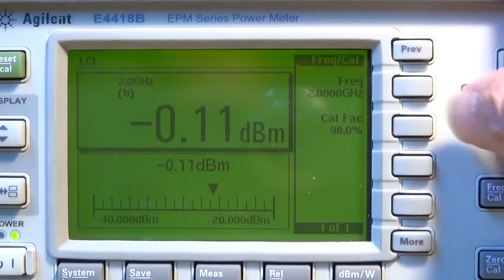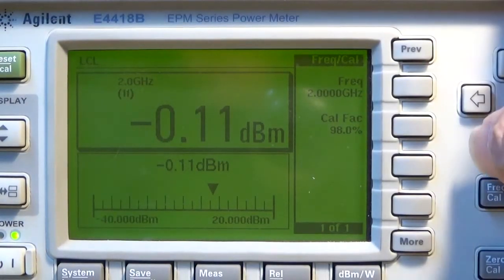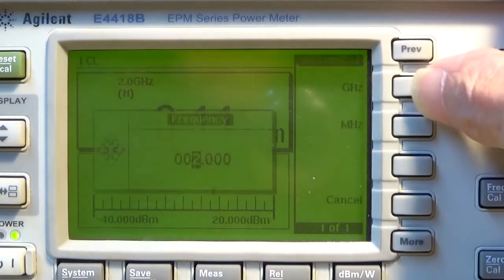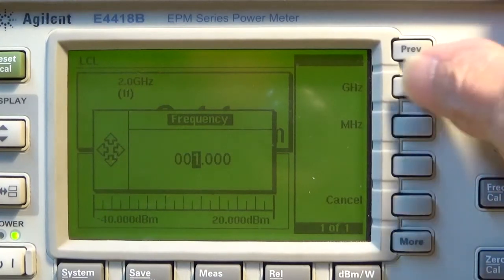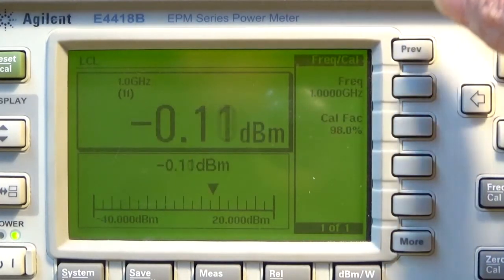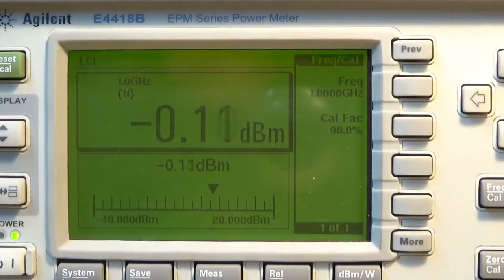Okay, now I've got to go through all this procedure again. Set it to 1 gigahertz, and it's minus 0.1 dBm. I think that's a reasonable output for an RF generator, because even they're not guaranteed more than about plus or minus 0.5 dBm accuracy across that whole range.